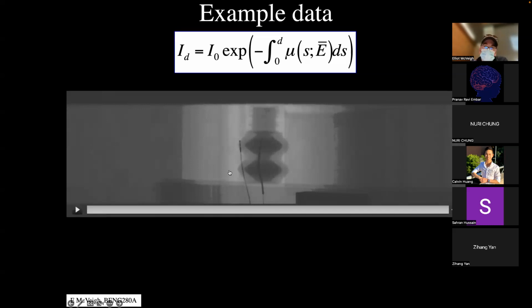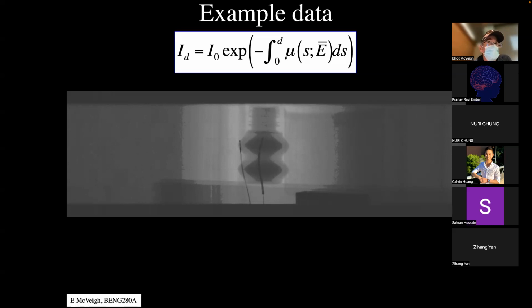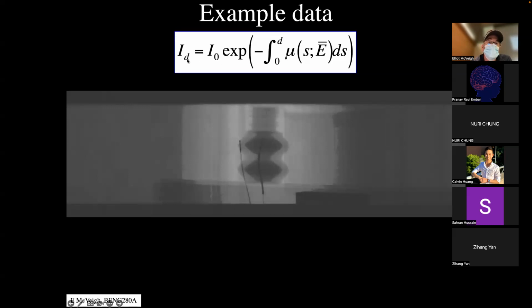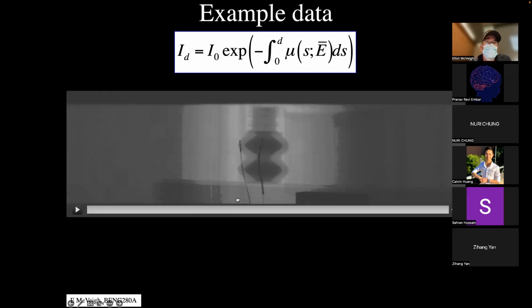This image here, as you'll note, has low values in areas behind the pacing leads, because the pacing leads absorbed a lot of photons. So this, in fact, is true raw data. This is not logged data. It is just the number of photon counts seen in each detector. Okay, so it's I_D equals I naught. So if I naught is the same at every location, then the relative values of this are just the relative amounts of photons seen.